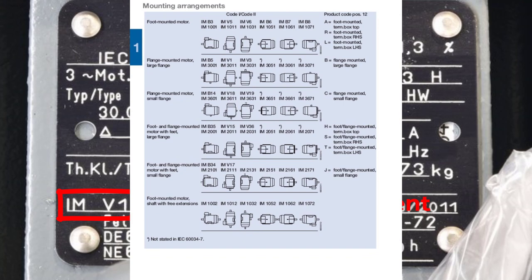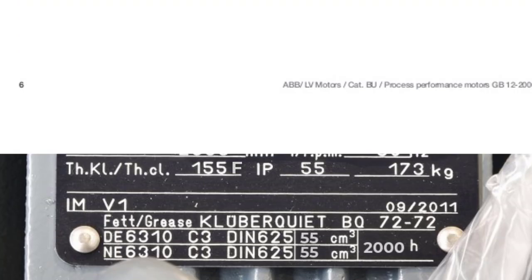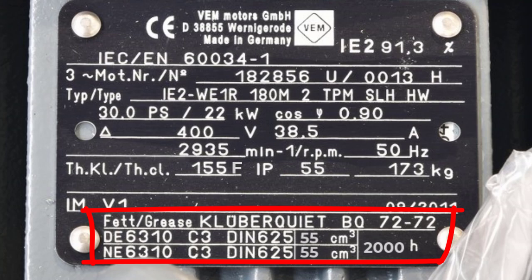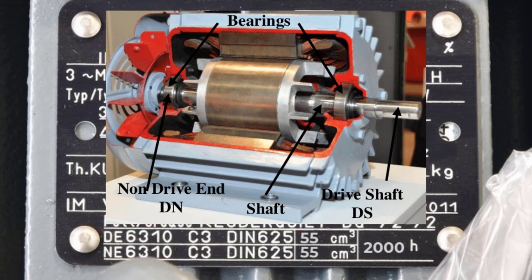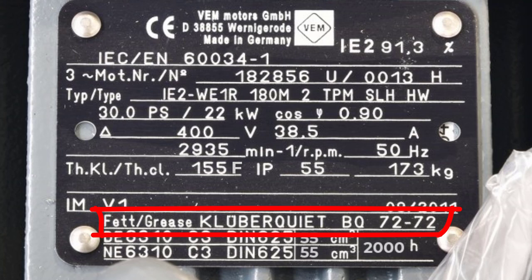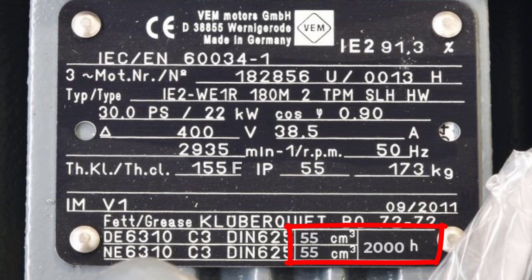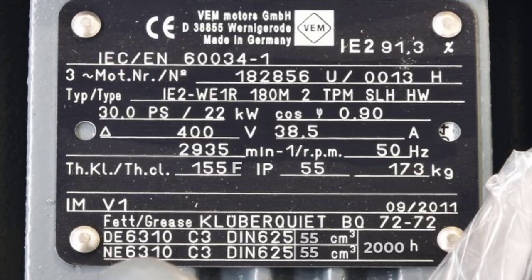IM V1 is the mounting arrangement factor, describing how the motor is mounted — foot mounted, flange mounted, or both, and whether horizontal or vertical. In our case, IM V1 is large flange mounted vertical. The bearing-related factors include the type of drive-end and non-drive-end bearings, the amount of grease to inject using a grease gun after specific running hours, and the type of grease to use. In this example, 55 grams should be injected every 2000 running hours.